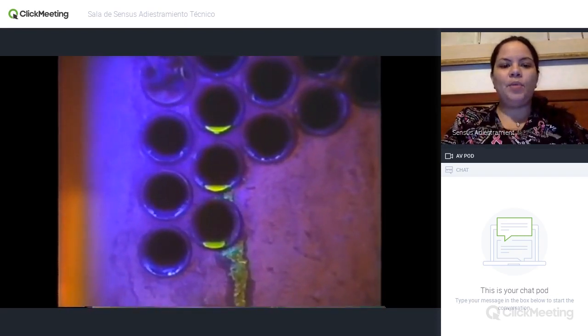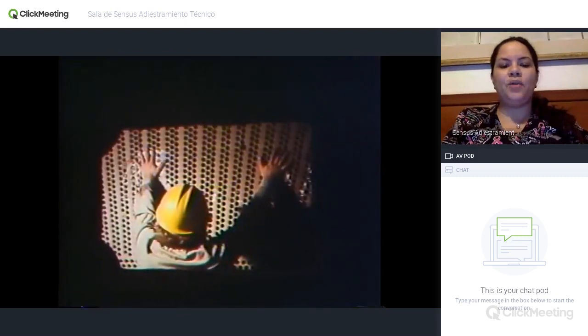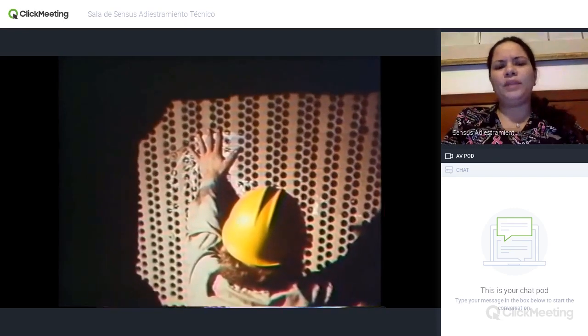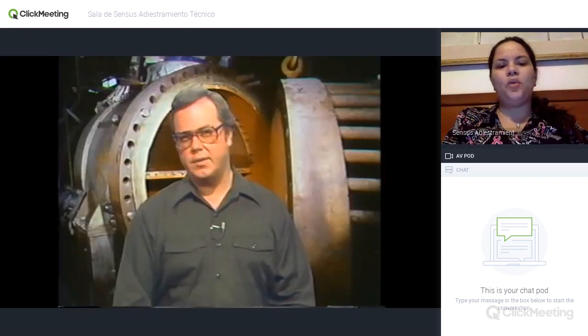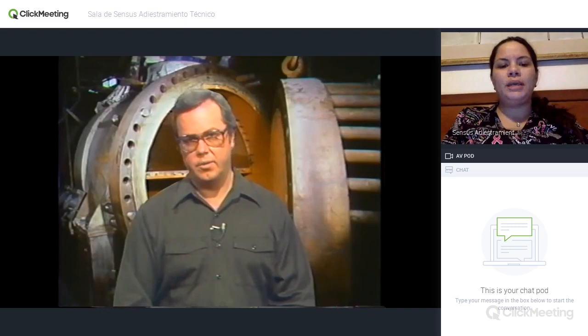Any leakage will show up where the dye comes through. On condensers and other heat exchangers which are run under a vacuum, a check can be used to look for leaks. It involves placing sheets of thin plastic wrap on the tube sheets to cover both ends of the tubes. This is done while a vacuum is drawn on the shell of the component.